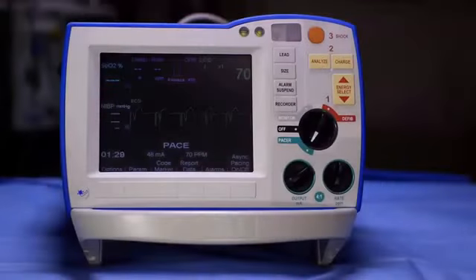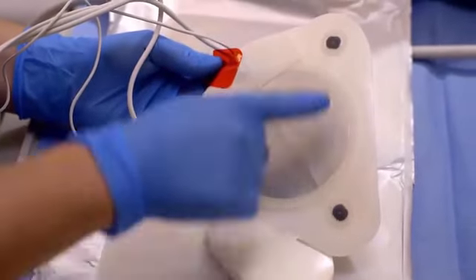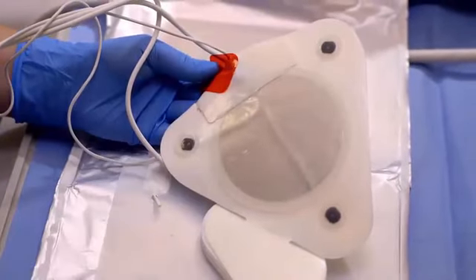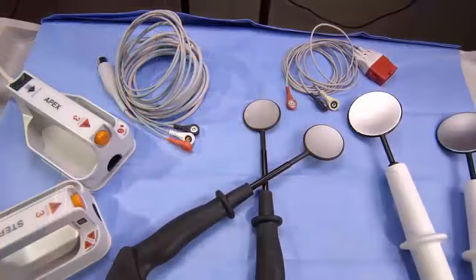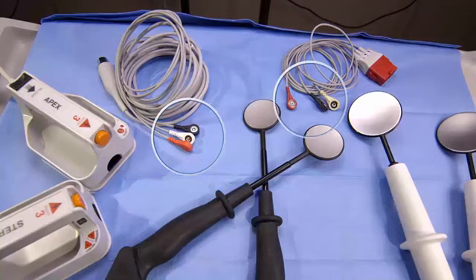Pacing. When the R-series is used with the one-step complete or pacing electrodes, a separate ECG cable is not required because the 3 leads are built into the front electrode pad. If these electrodes are not used, you must first attach an ECG cable to the device and place the 3-lead ECG electrodes on the patient.